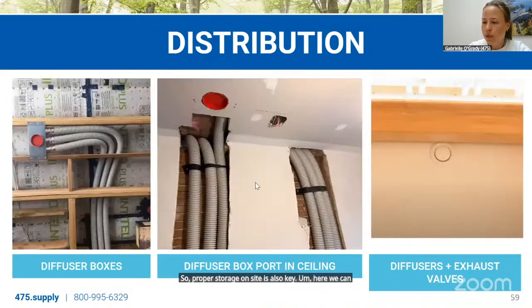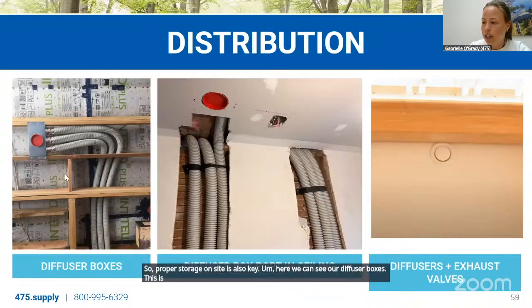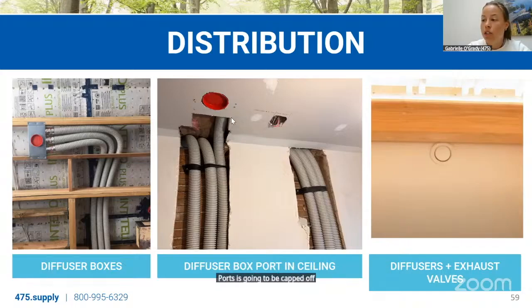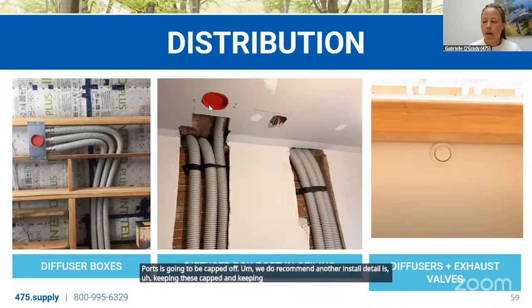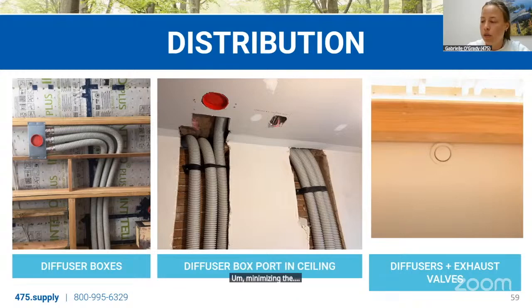Here we can see our diffuser boxes. This is a 3-port again. This one that's hidden up in this wall here is a 2-port, but we only have 1 duct going to that, so one of these ports is going to be capped off. We do recommend, another install detail, keeping these capped and keeping the top of the unit sealed as well while construction is happening, minimizing the amount of dust and debris that can get into the unit.